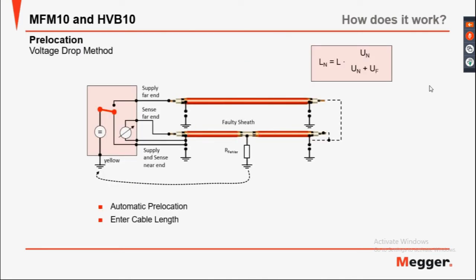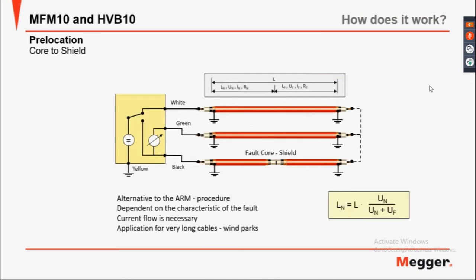The voltage drop method. Pre-location from core to shield: an alternative to the Murray procedure, depending on the characteristics of the fault. Current flow is necessary in application for very long cables, usually offshore wind plants.